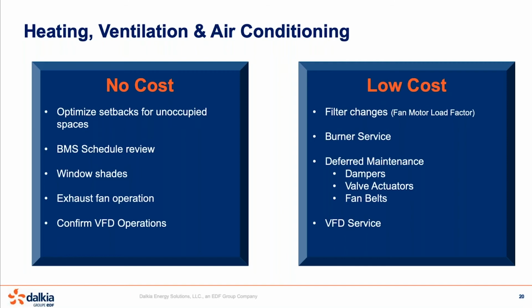Window shading where possible. So if there are shades in a building and there's no one there, we can reduce the air conditioning load by dropping the shades. And another thing that we see frequently is that VFDs have been installed, and there's a fault at one point, and so they just go right into bypass. So it's a great opportunity right now to recommission those VFDs to ensure that they are operating and are allowing you to leverage the shoulder seasons, especially in the spring here.